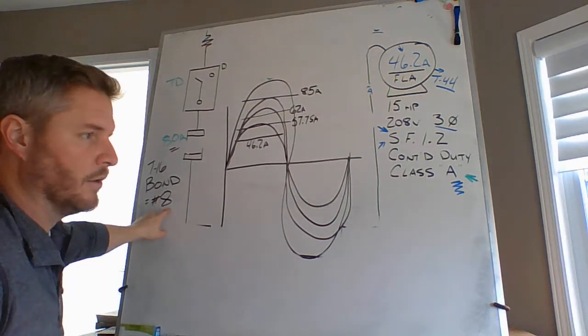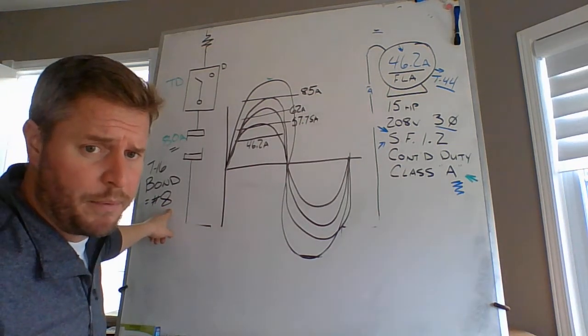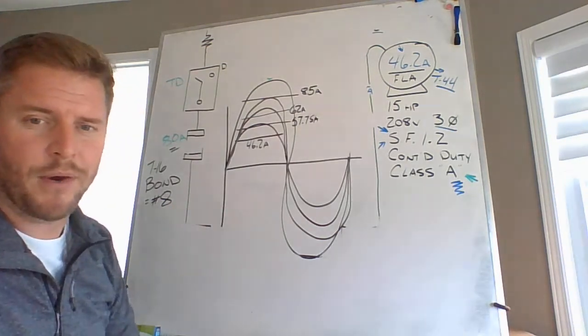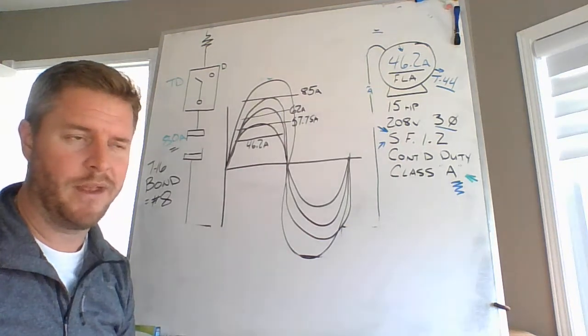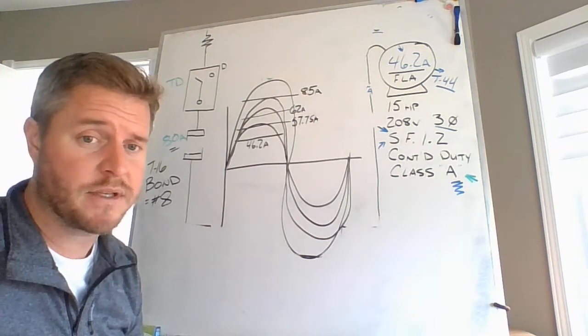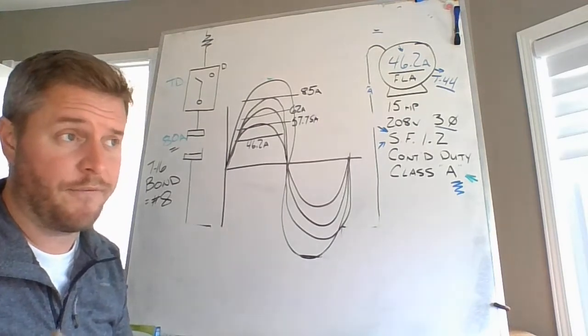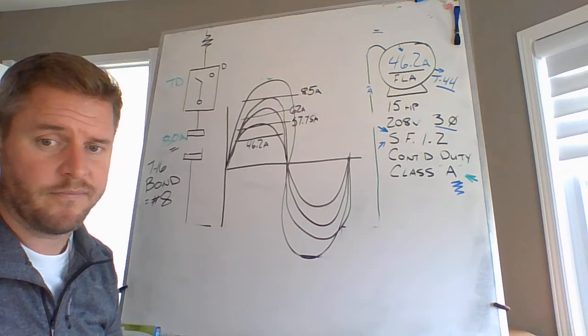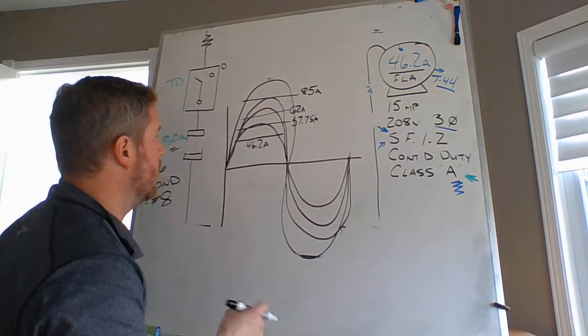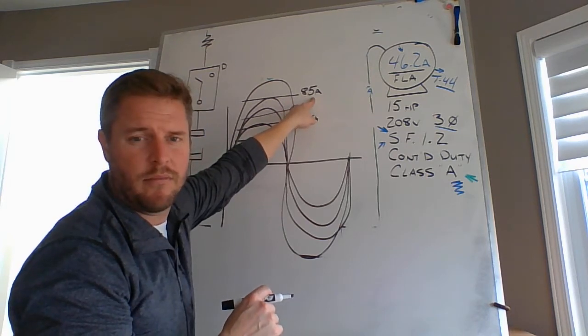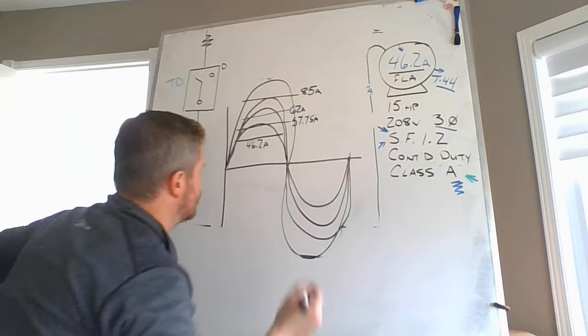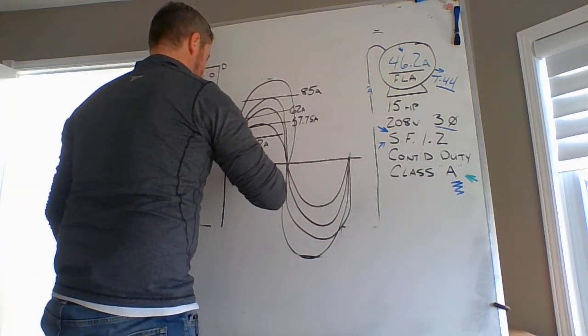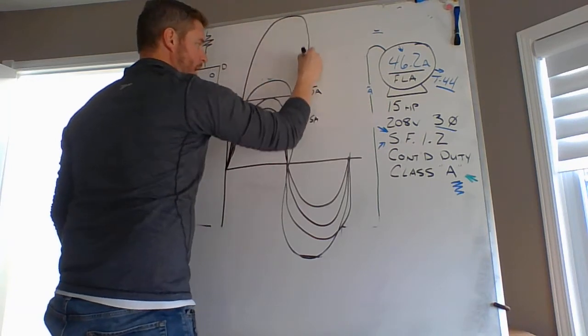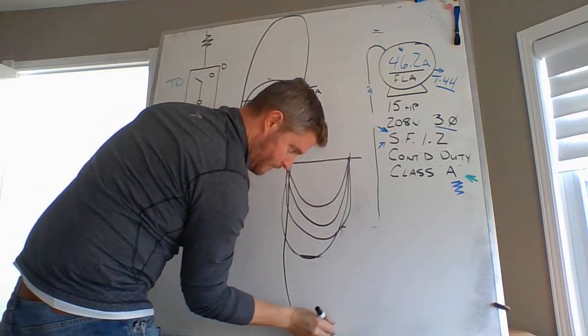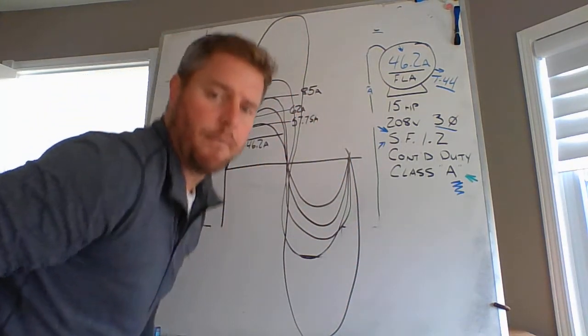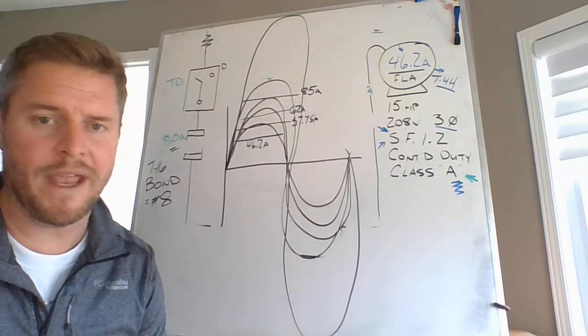That number 8 bonding conductor will handle an incredibly large amount of current for a very short period of time, just like all of your conductors will. A 14 gauge conductor will handle 100 amps, but for a very short period of time until it physically melts. Usually what ends up happening with a short is we don't draw 85 amps. We don't draw 100 amps. We don't draw 200 amps. What usually ends up happening with a short is we draw all the amps. As many as could possibly flow, we draw all the ampacity.